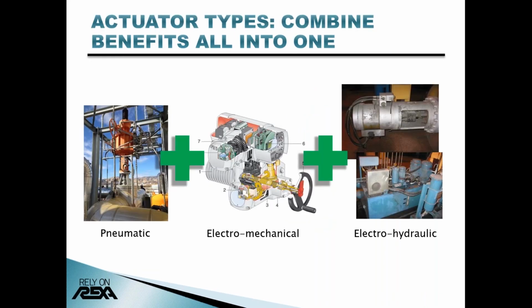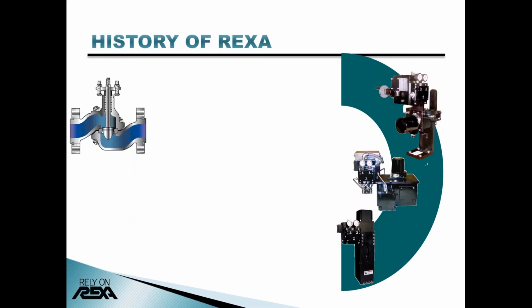REXA combines the benefits and capabilities of each of the actuator technologies into one. The simplicity of pneumatics, compact installation of electromechanical, and the fast stroking, high resolution, high duty cycle of hydraulics. How REXA came to be was from identifying control issues in a process loop and looking for methods to fix those problems. Valves were often, and still are, blamed for poor control in a process. What if the valves were not the only reason for having control issues?